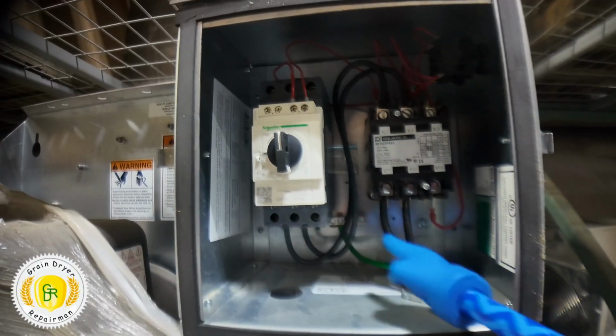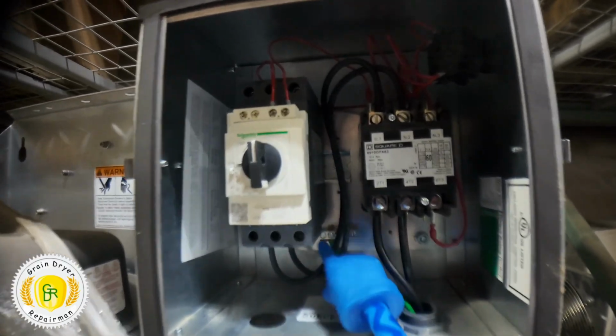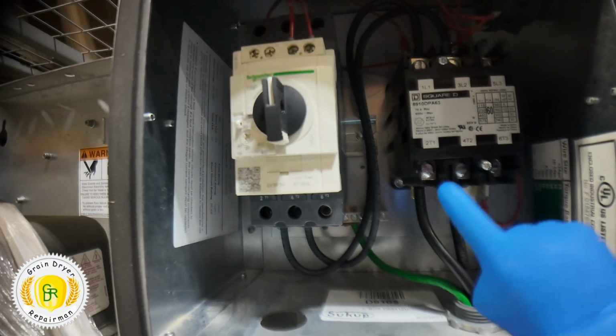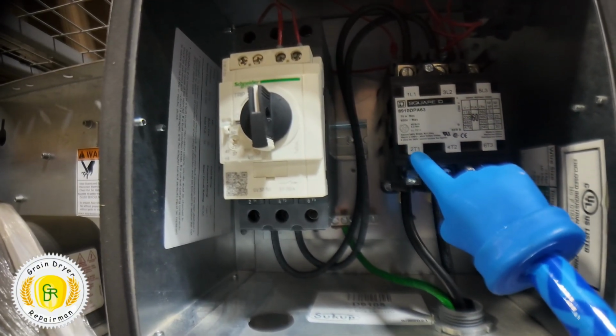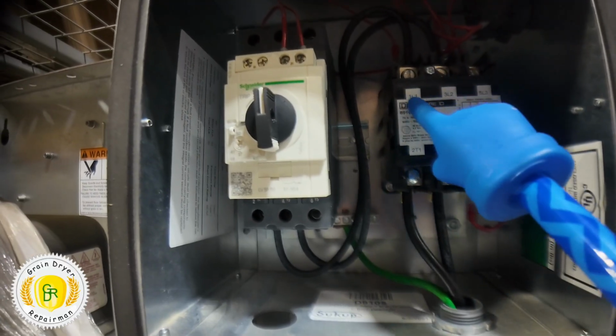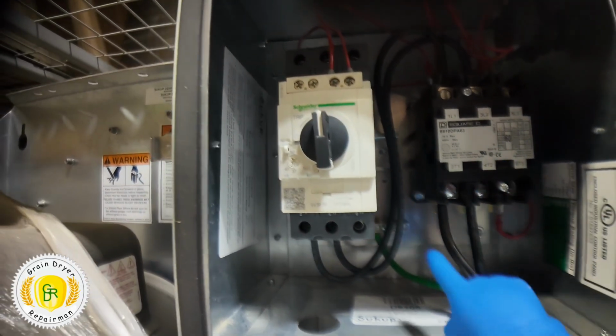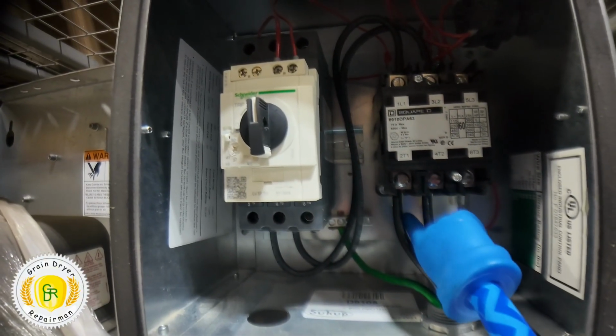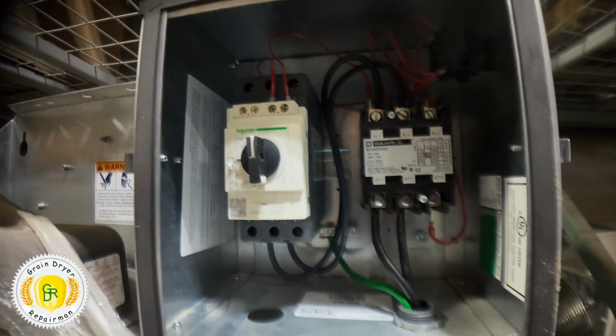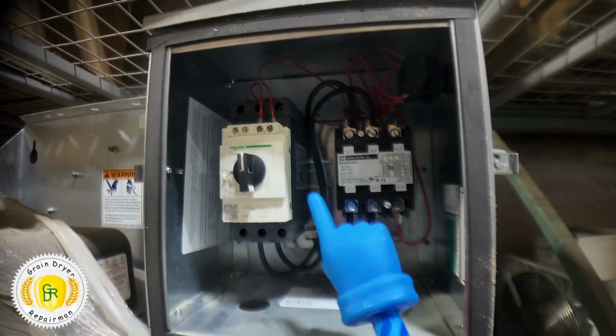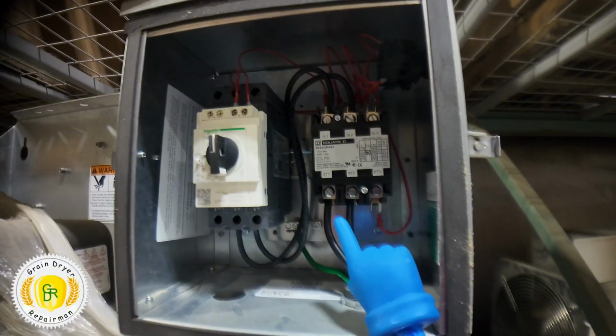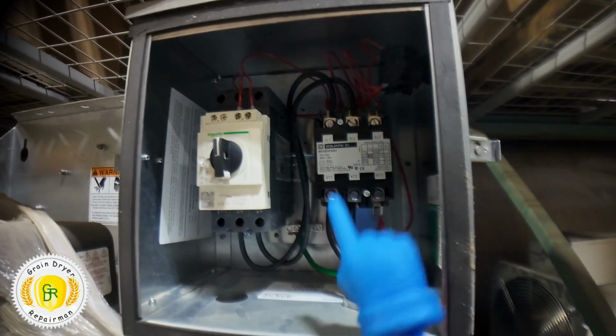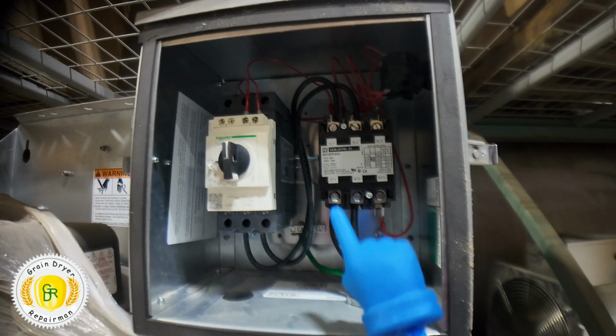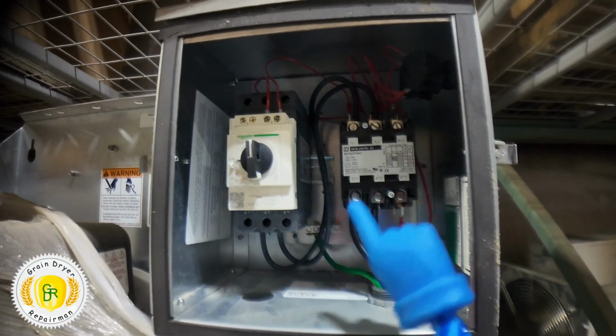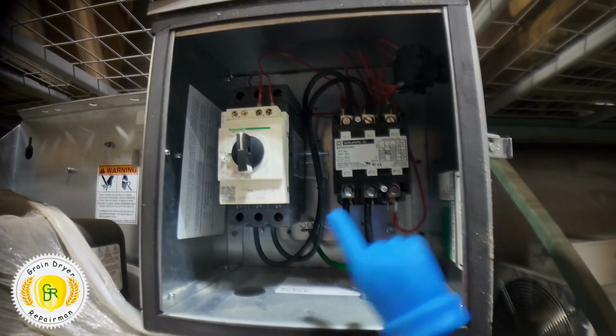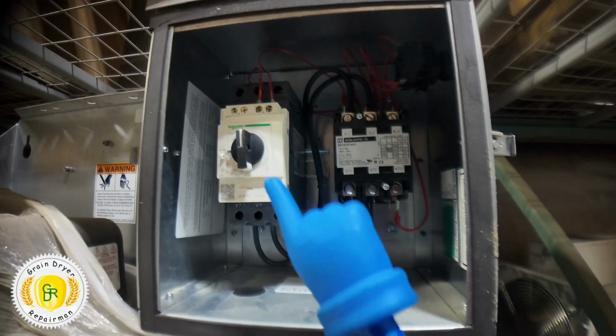So you're gonna connect your ground to the ground bar. You're gonna connect your black wire to T1. This says T1. Do not connect to any of the L's. Must be T1. There's this connector on the back there for connecting your wire to T1. That's where the black wire connects. If this is the case, your white wire needs to be connected to a neutral from the breaker box, which a qualified electrician needs to run. So a qualified electrician needs to provide a neutral wire to the fan box if running a burner on a single phase fan.